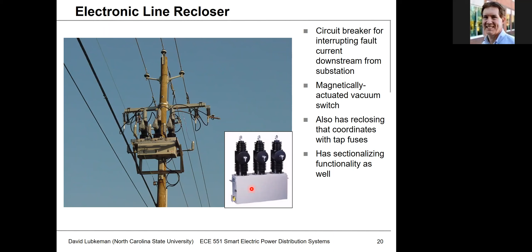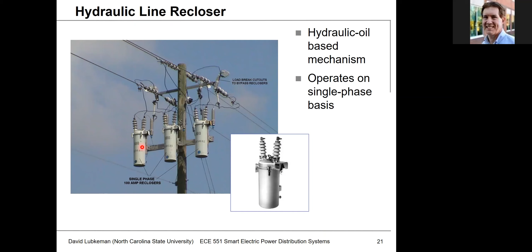There's also older types of devices out there where instead of using vacuum bottle technology, you would use an older oil circuit breaker type of technology. These are referred to as hydraulic line reclosers. They're not electronic, that's all kind of mechanical based. This is used a lot of times for single phase, though you might still see 3-phase out there. It's not as flexible as an electronic device with an electronic controller on it, but they're highly reliable. If you want to have something located remotely, this might be a good option for single phase or 2-phase.